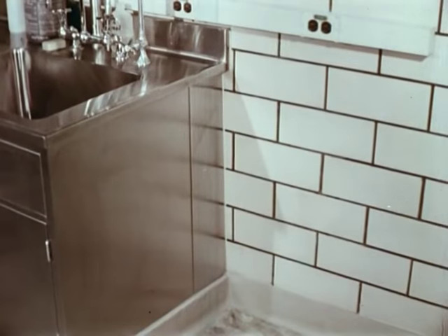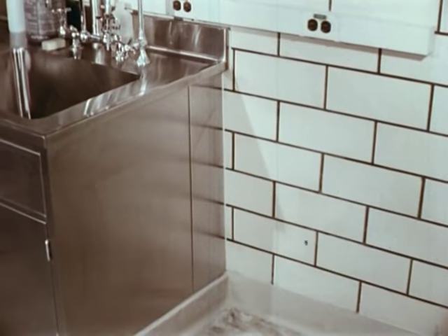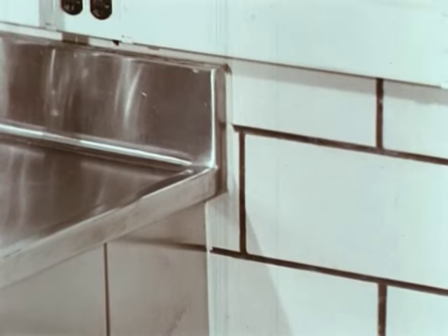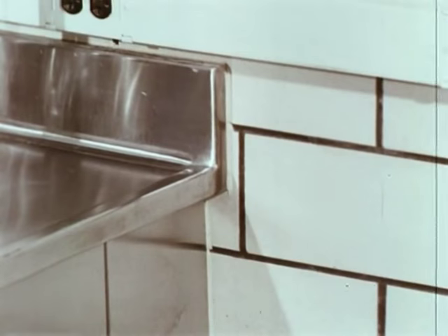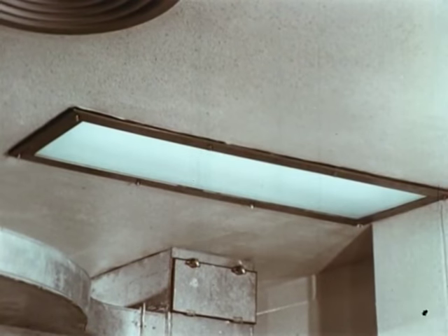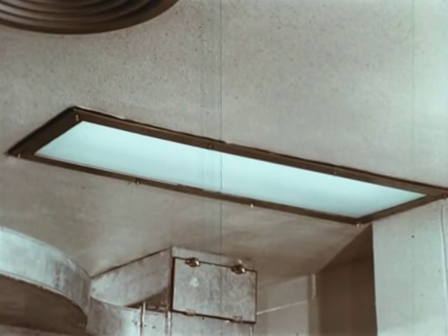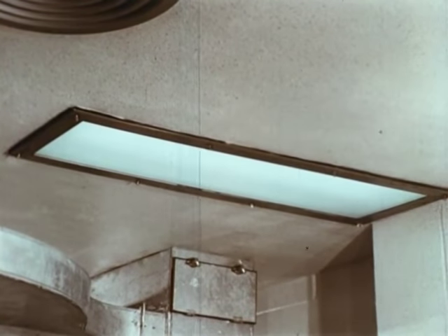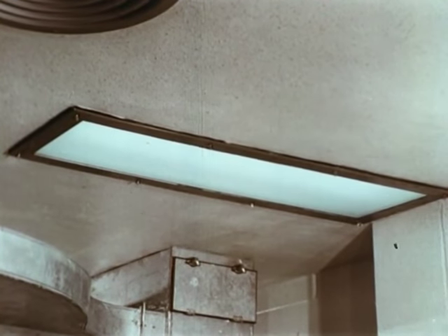Walls, wall curbing, and ceiling should be free of cracks. Often a monolithic covering is used on the floors. In order to facilitate cleaning operations and to prevent leakage of organisms from the lab area, casework should be sealed to the wall. Equipment not sealed to the wall, such as cabinets, tables, and chairs, may be mounted on wheels to facilitate decontamination and cleaning. Lighting units and other features that penetrate the barrier walls must be designed so as to assure adequate physical separation between the contaminated and clean zones.